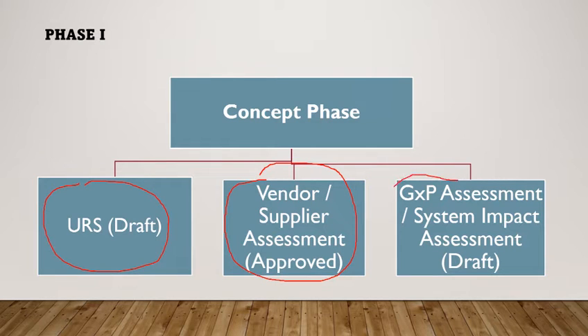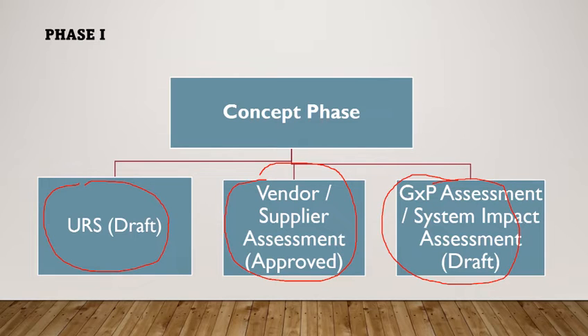Next, we need to perform the GXP assessment. This document identifies the GXP impact and which GAMP category the software falls into — category 1, 3, 4 or 5. It also evaluates and justifies whether the system is required to follow the electronic records and electronic signature requirement mentioned in 21 CFR Part 11 regulation. Based on all these documents, you can have a basic idea of the system, which will help you validate the system and initiate the in-house change control procedure to implement the system.